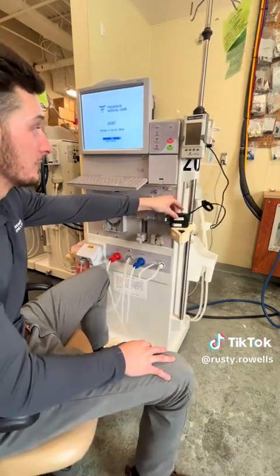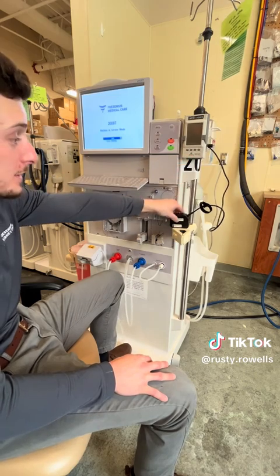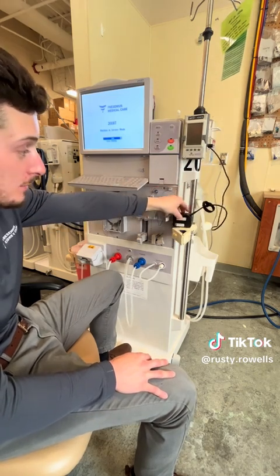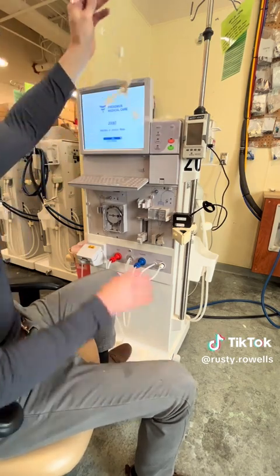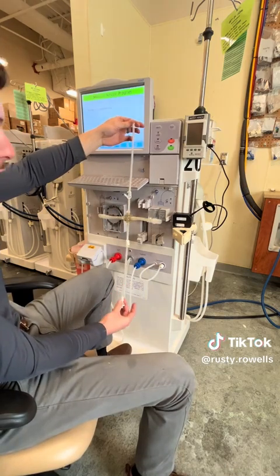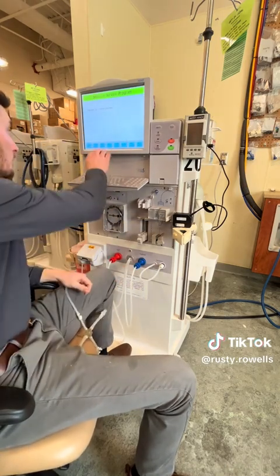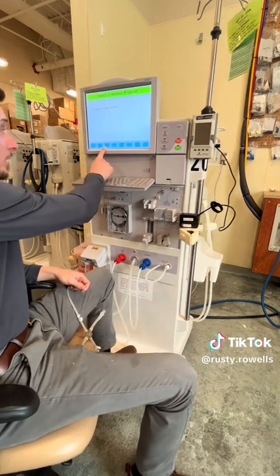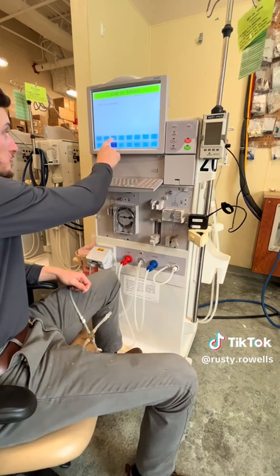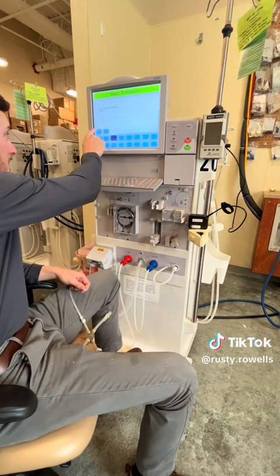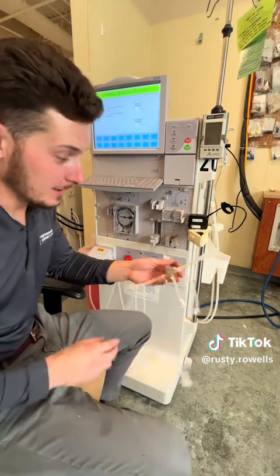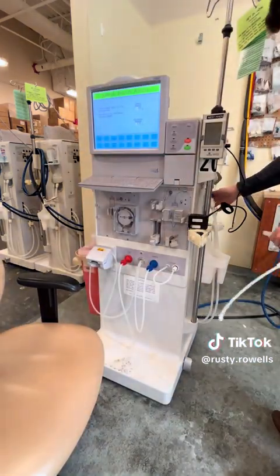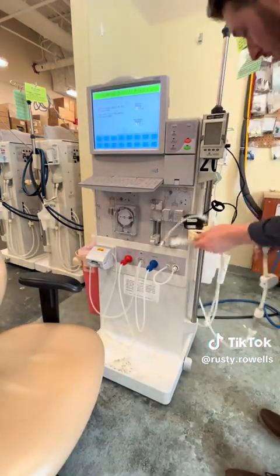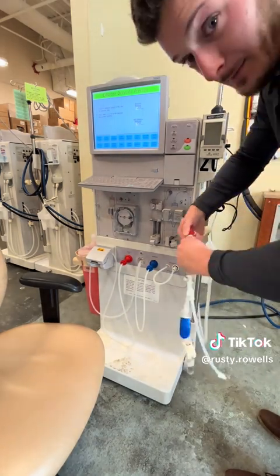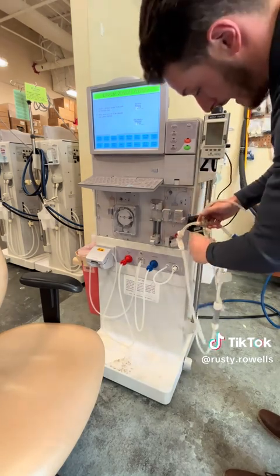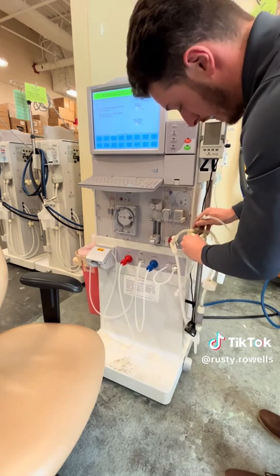So what we've got here, we've got our 90XL meter with our pressure gauge, pressure module attached to it. And then to do this calibration, we have to have a 4-way. So we're going to go straight to the calibration. You're going to go to calibrate sensors, pressure transducers, and dialysate pressure. So now we're going to get ready and hook this up. We're going to take our Hansens out of the shunt door and connect them to the 4-way, and we're just going to hang it right here on the dialyzer holder.